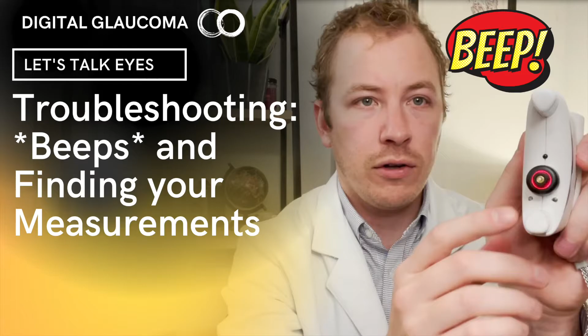I've got an iCare device here, and I'm going to load a probe in, and then we're going to go through a couple troubleshooting things. There's three main tones and noises that this makes. It'll do 2 beeps for bumping an eyelash or not getting good contact. It'll do 3 beeps for too far away, meaning the cheek support or the forehead support is too high, like a 10 would be further away than an 8 or a 6. So if it's too far, it'll beep 3 times. And then if it's too close, it'll beep 5 times really quickly. So if you hear just a bunch of beeps, it means it's too close.